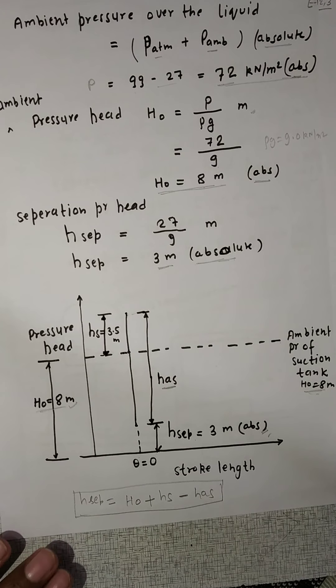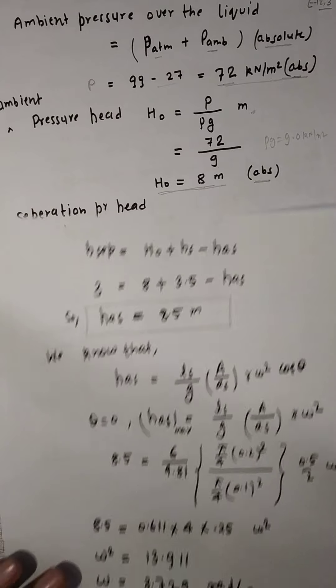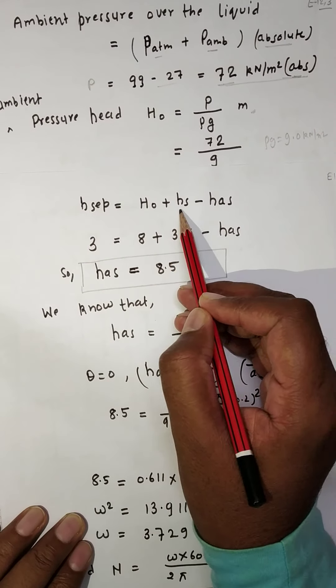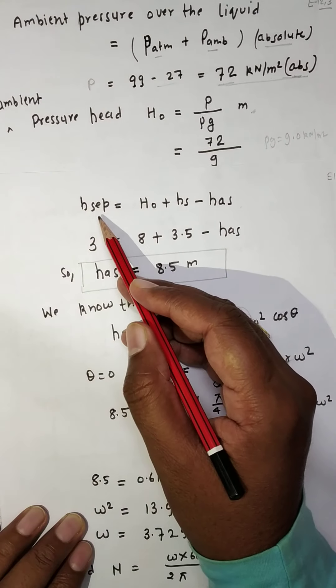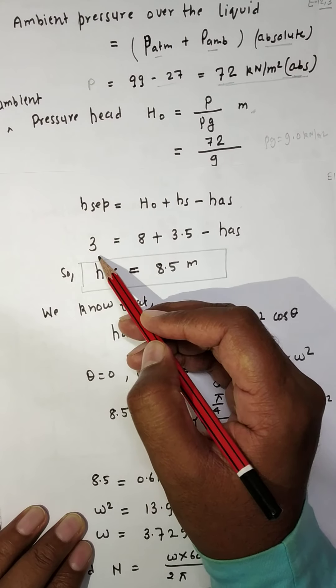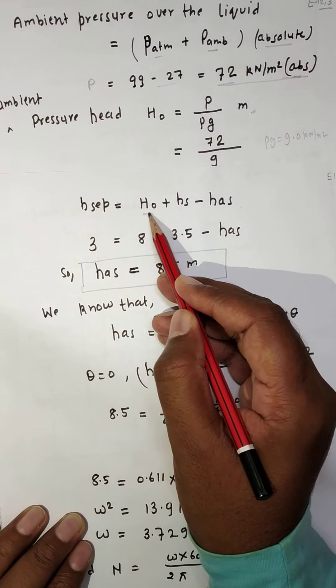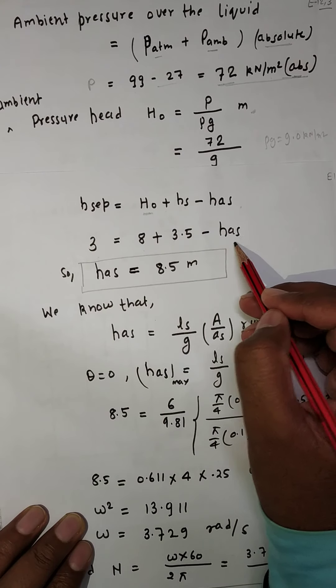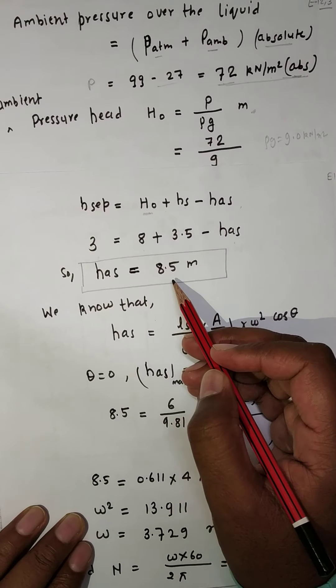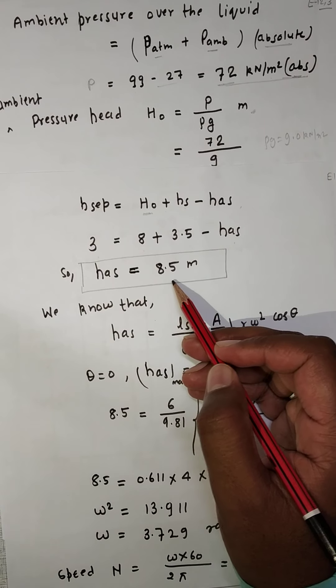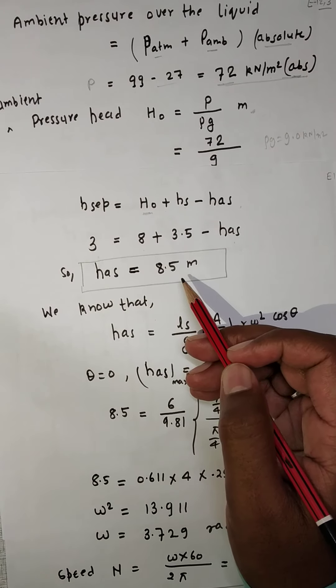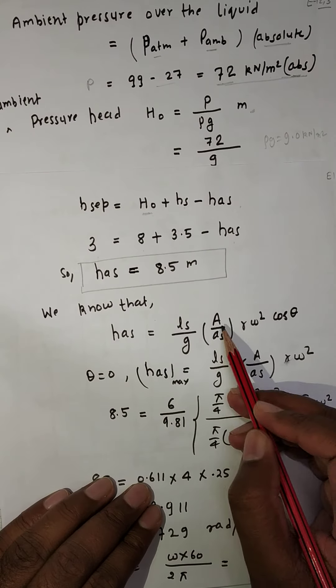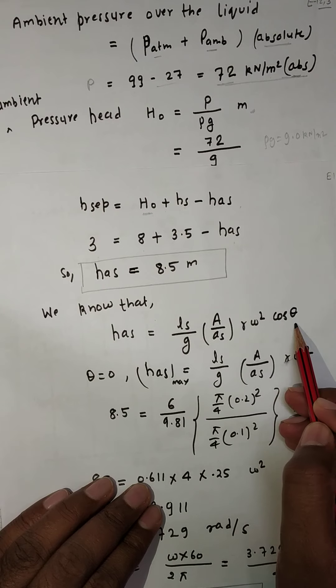So the separation head equation is: h_sep = H₀ + h_s − h_s_max. The separation head value is 3 meters, the ambient pressure head H₀ is 8 meters, and the suction head h_s is 3.5 meters. Therefore, h_s_max = 8 + 3.5 − 3 = 8.5 meters. We know that h_as = (l_s / g) × (A / A_s) × r × ω² × cos θ.